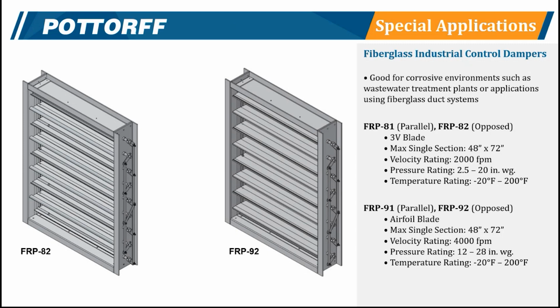Now, these are pretty costly dampers, and they do have a bit of a longer lead time. So they're really great for your wastewater treatment plants or anywhere where they're using fiberglass duct systems. But for most regular industrial applications, they may not be a competitive bid. So we really only recommend it when you absolutely need it or when the engineer specifies it. And really, we see this mostly with wastewater treatment plants, or say they're using fiberglass duct systems, whether they're underground or above ground. But fiberglass duct systems typically are underground for those types of applications where they will be protected from, say, UV rays and things like that.